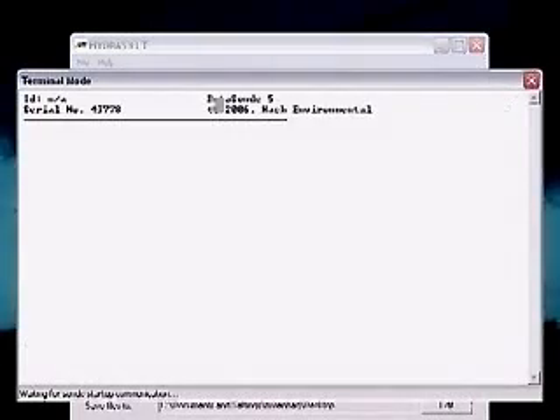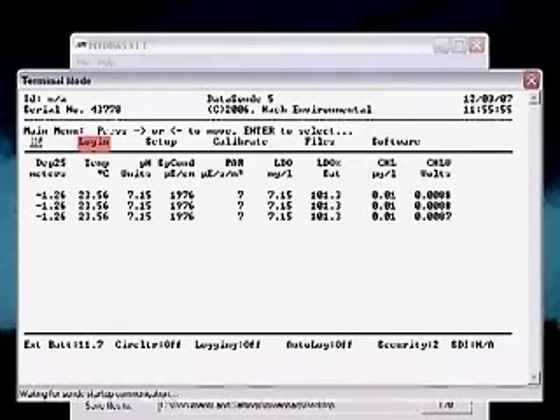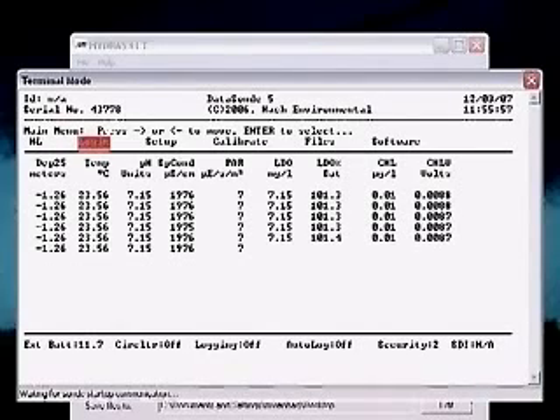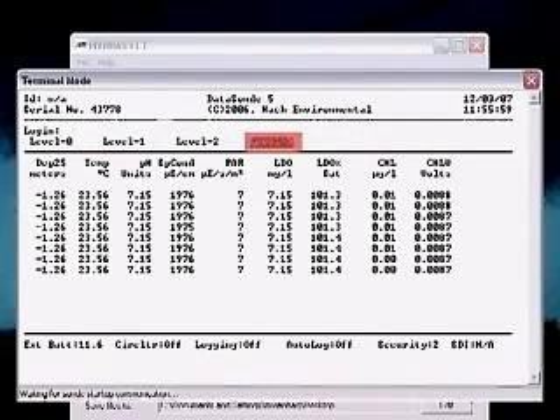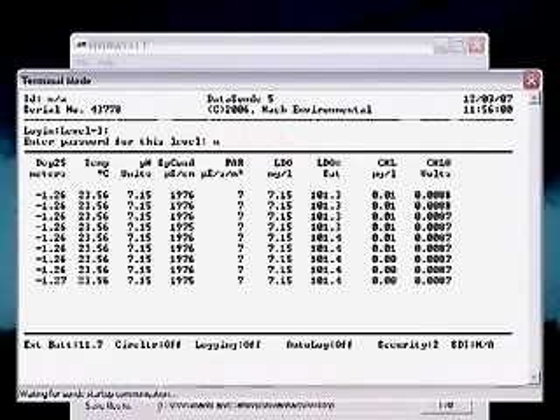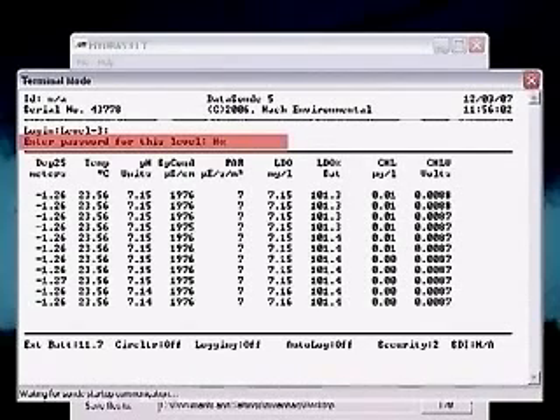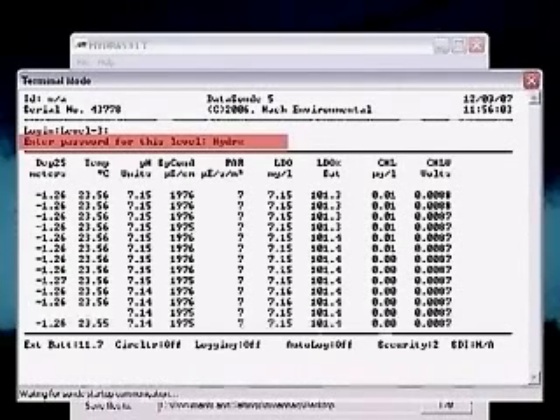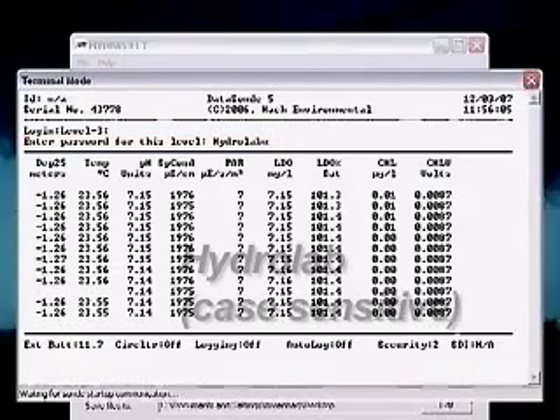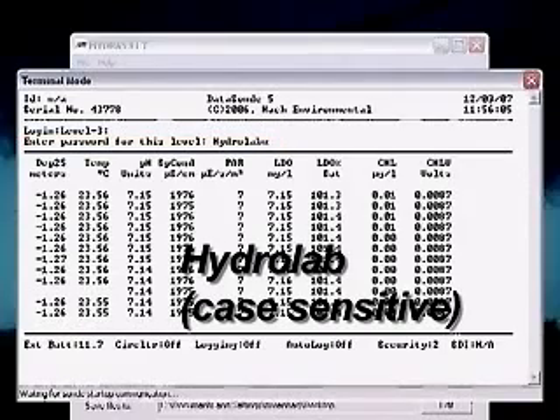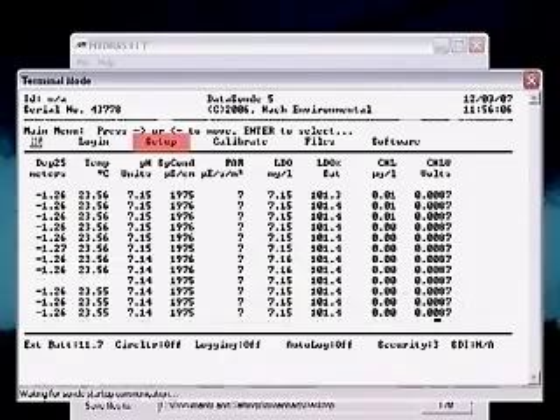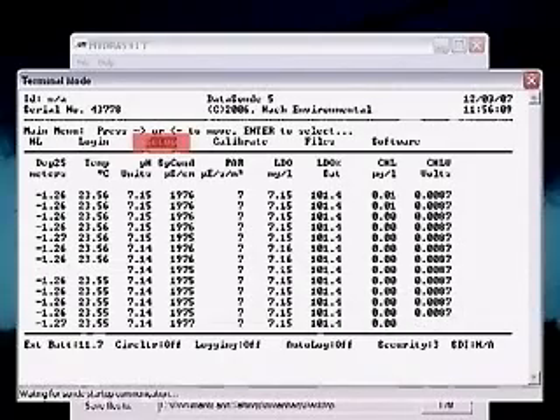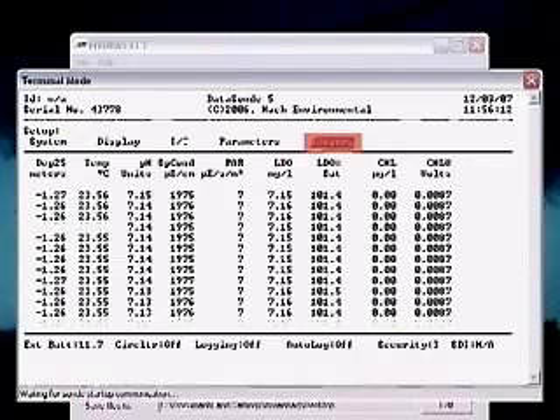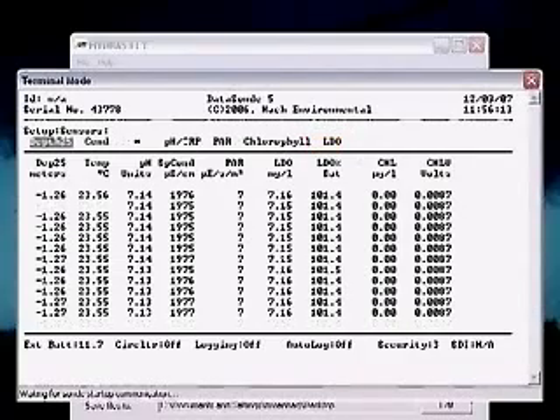Using the arrow keys, highlight Log In and press Enter. Highlight Level 3 and press Enter. Type the password and press Enter. The default is Hydrolab and is case sensitive. Use the arrow keys to highlight Setup and press Enter. Highlight Sensors and press Enter.